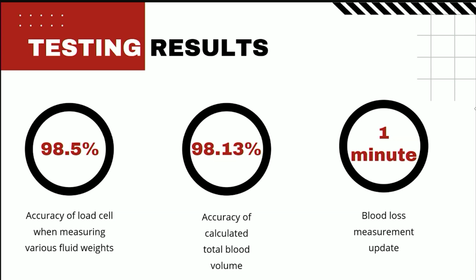We do recognize that there are some limitations. For example, the weighing trays that weigh the sponges and clots currently assume that all the fluid that's collected in those clots is blood, and that can lead to overestimation of blood loss. Additionally, we haven't been able to test the long-term durability of our device, and we recognize that there are still limited risk managements, and we need fail-safes for edge cases like liquid overflow, clogging, and sensor malfunctions. And so, pathway to implementation, we obviously want to add those risk management mechanisms, update the user display so that the user will have options for certain settings of the device. And I will be traveling to Uganda this summer to meet with our Ugandan teammates and finalize the design with local materials and conduct V&V testing.